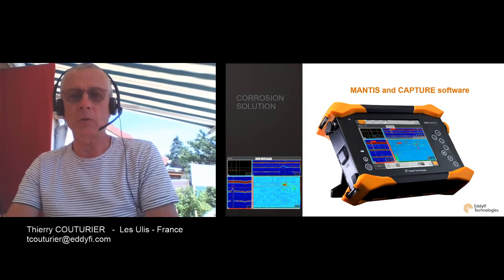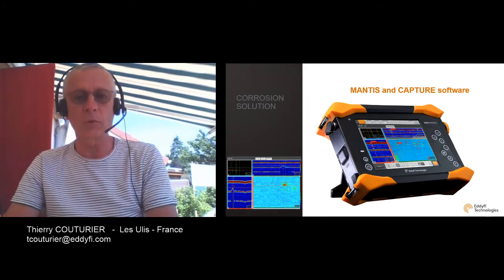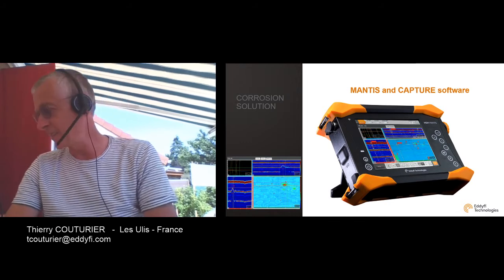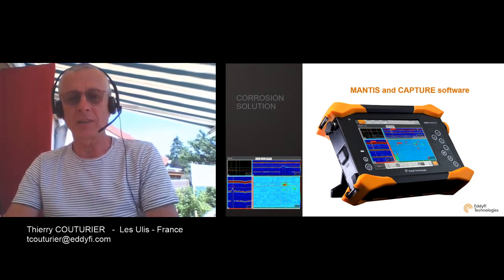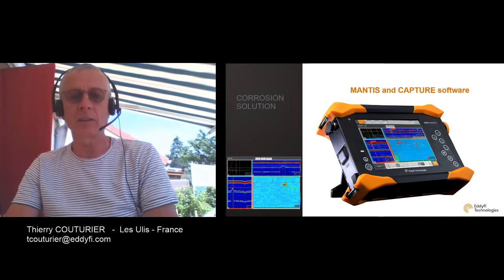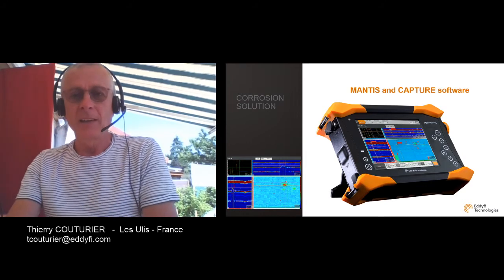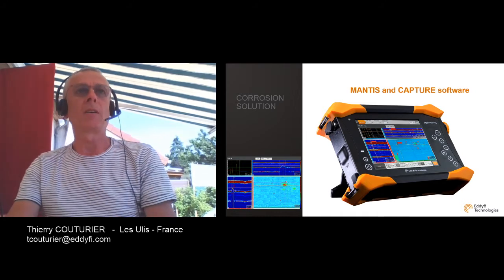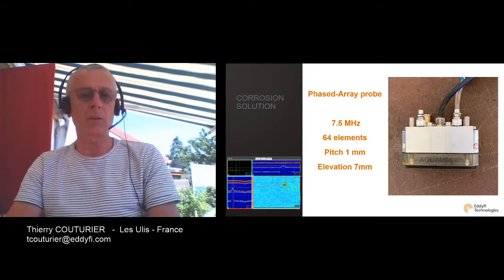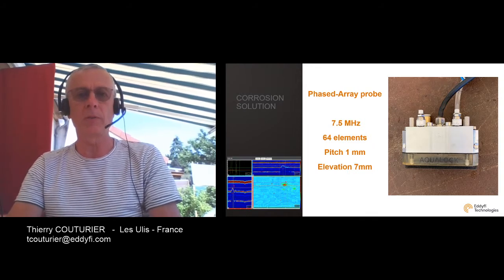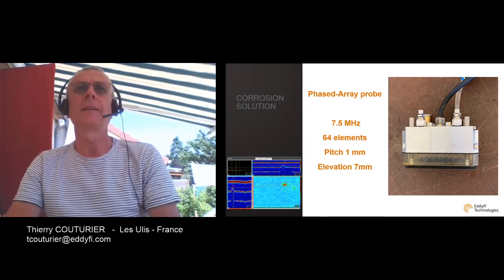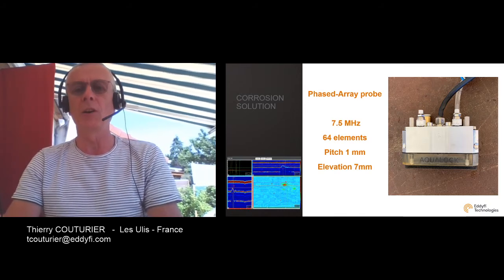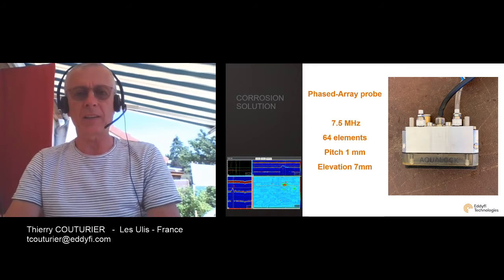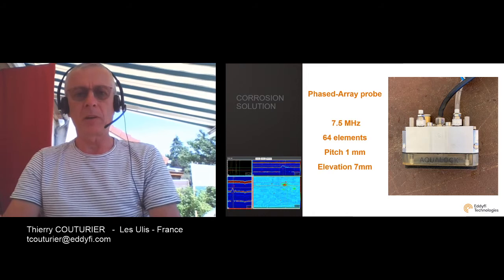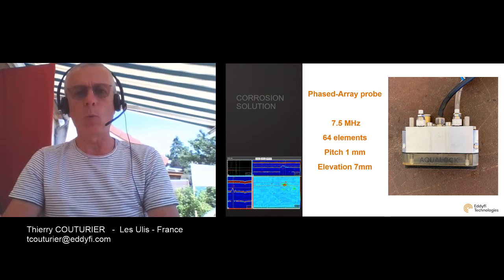It's a new housing so that you can perform corrosion inspection, well, inspection on site in an industrial environment. It's quite a light unit and at the same time robust, we hope so. The setup I have comes with this probe, a phased array probe, 7.5 megahertz, 64 elements. Pretty well known for those who have used similar techniques from other manufacturers maybe. The pitch of this probe is 1 millimeter and the elevation 7 millimeters.